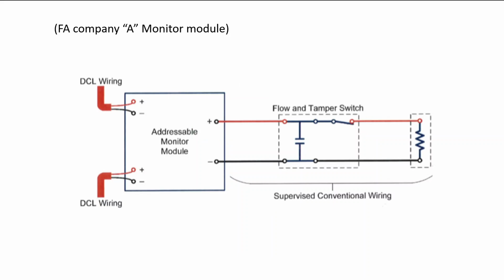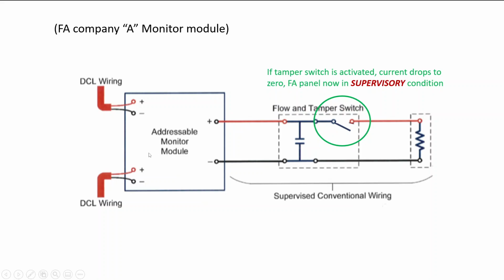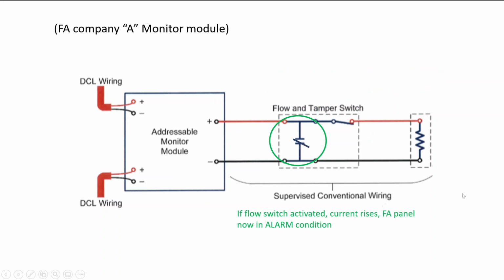The first one we're going to call Company A fire alarm. Maybe that's Edwards or Kidde or I don't know. There's like half a dozen different brands out there. But Fire Alarm Company A produces an addressable monitor module, and in this one, they require only two connections. These two connections will be monitored for any sort of wire breaks, and there's an end-of-line resistor, and built into each of our components is usually the actuating device and the tamper. And so, just like all other conventional wiring, there's going to be supervisory current, and if the tamper switch is opened, this particular module will be programmed to recognize that this is a supervisory condition because of what I have connected. So it's something that has to be programmed into it. If instead the contact closes in this being a flow switch, that should initiate an alarm, and that's because of the current rising in this conventional branch.